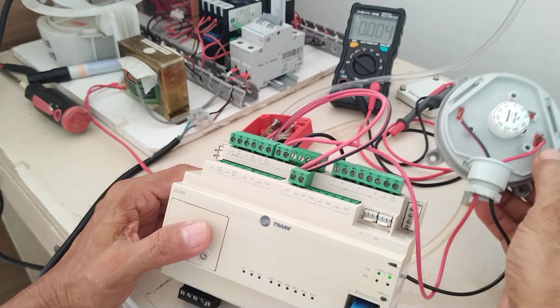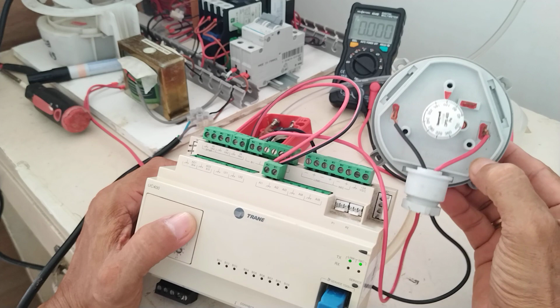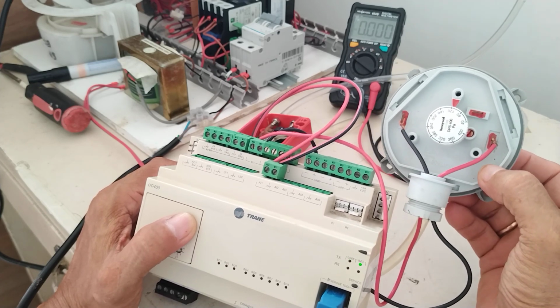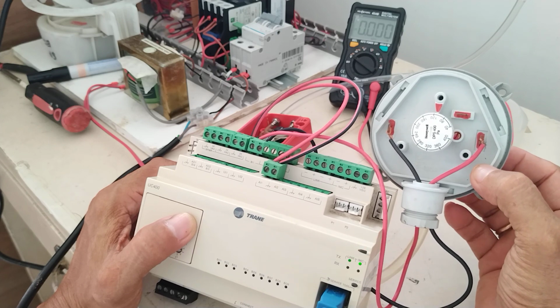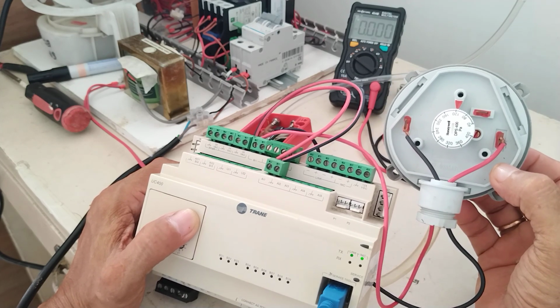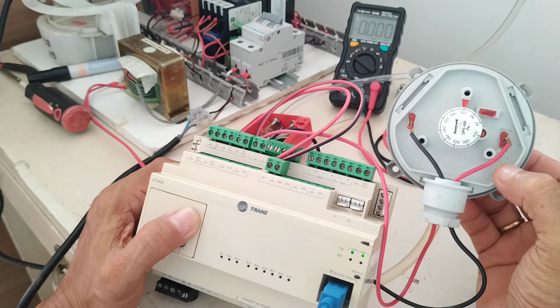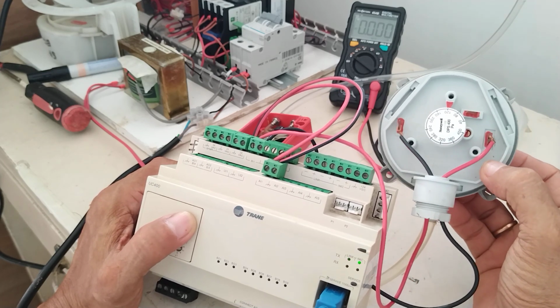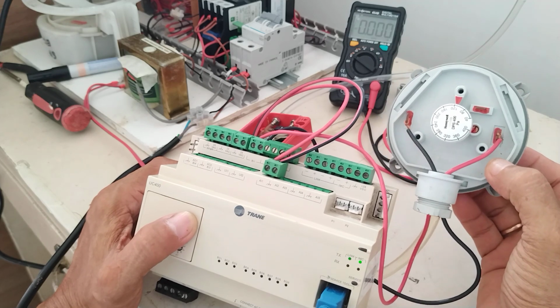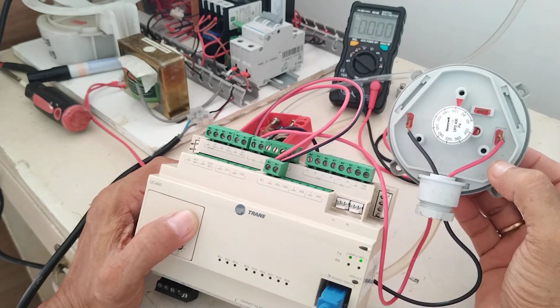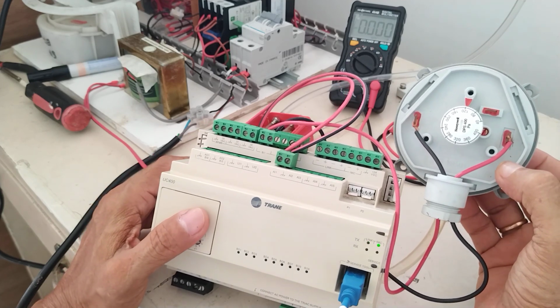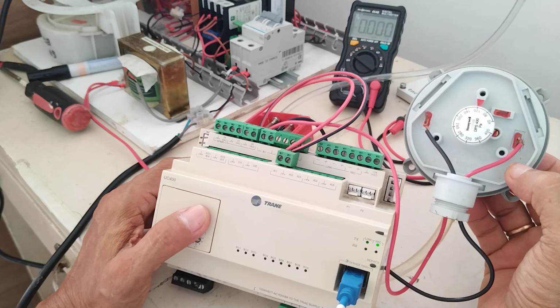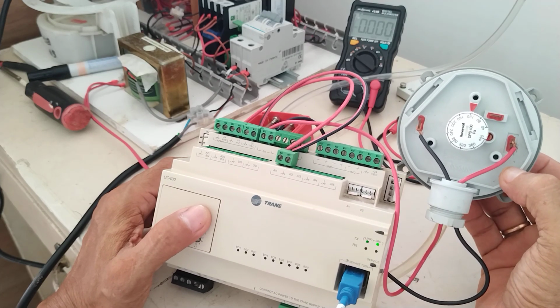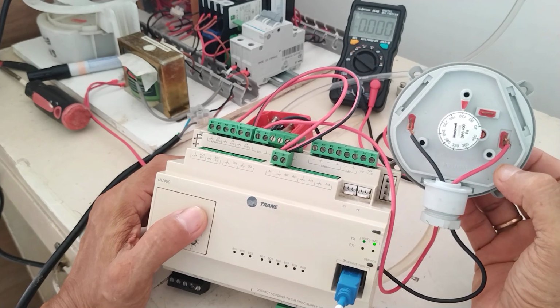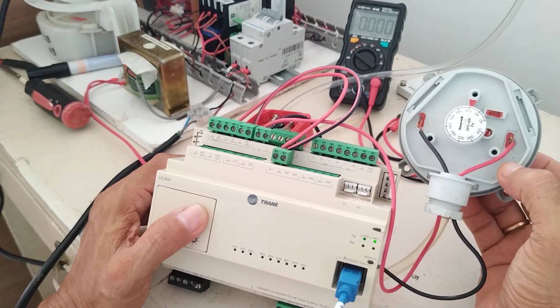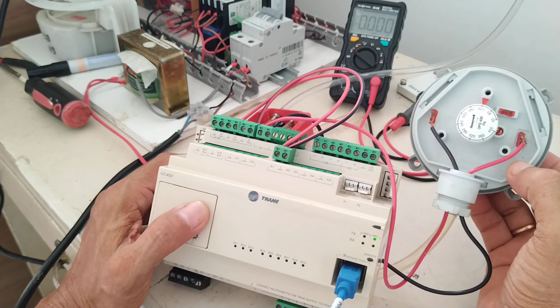So guys, by the way, as a BMS engineer, one of your scopes is to do the cable takeoff, okay? Now, we have what we call BMS monitoring cables. In my previous projects, we are using Belden cable. So for monitoring points, we are pulling Belden cable. As I said, this will be one of your scopes. Meaning, as a BMS engineer, you will be the one to do the takeoff for the cable requirement of the project. Meaning, you will try to estimate how many rolls of cable you need to provide in a project.